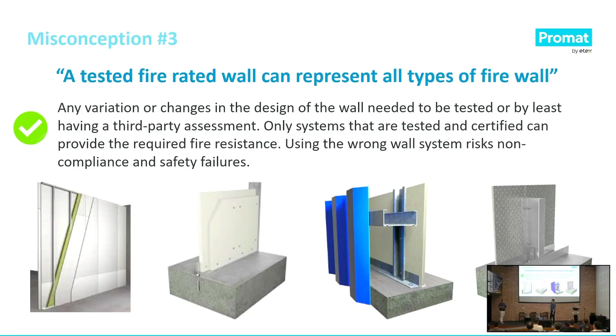For my export market, some countries still accept integrity only for fire rated walls. Depending on the criteria, we propose differently. I could have a 2 hour fire rated wall fulfilling integrity only with one layer of 9mm board and a 50mm stud, total thickness 59mm. But for another 2 hour fire rated wall where you need to fulfill insulation criteria, our system requires about 136mm. So always clarify the application area and the exact rating needed—stability, integrity, insulation are the criteria measured during a fire test. We have different wall systems; some slim ones fulfill both integrity and insulation, while others fulfill integrity only.